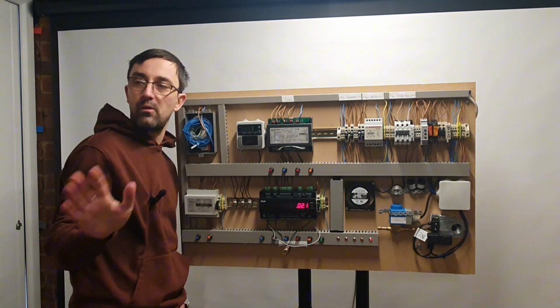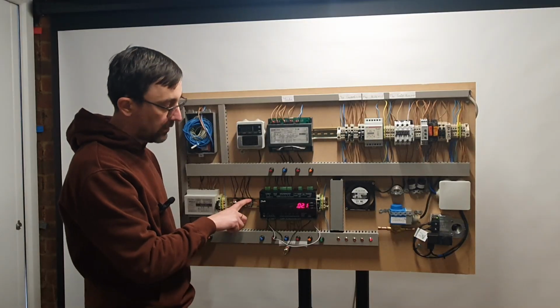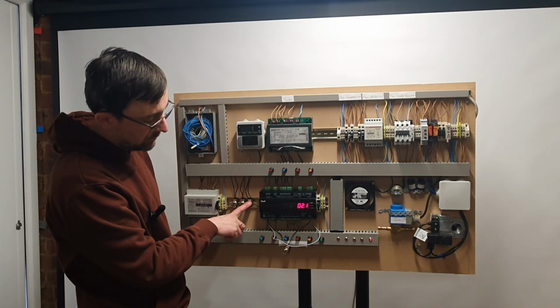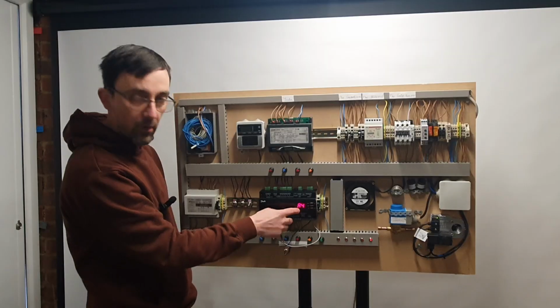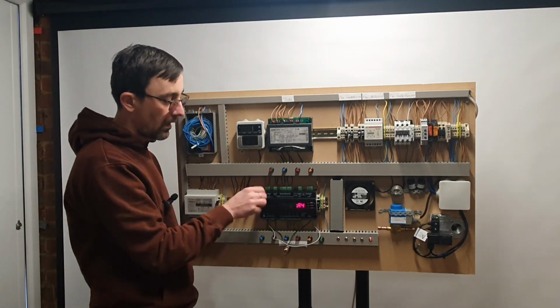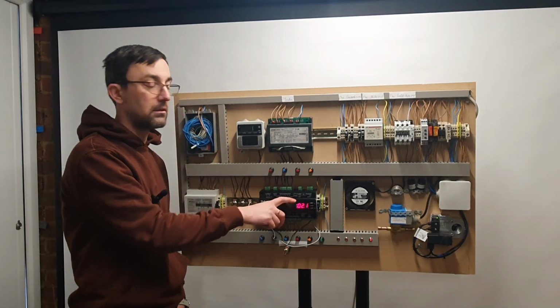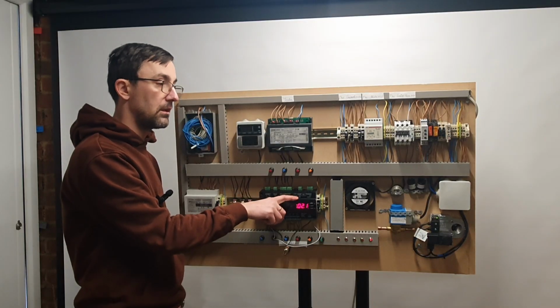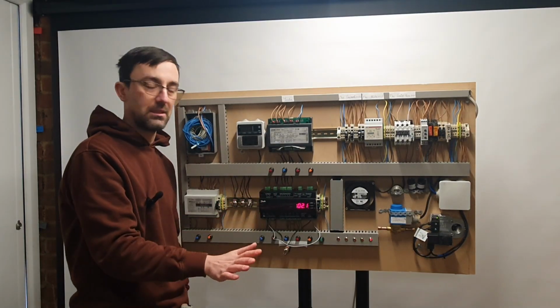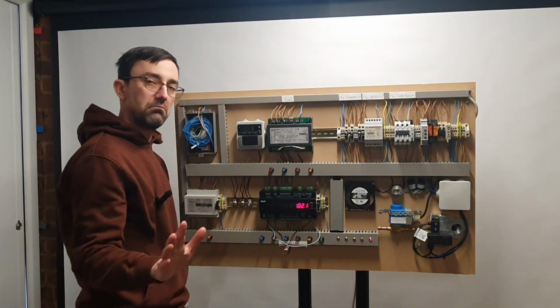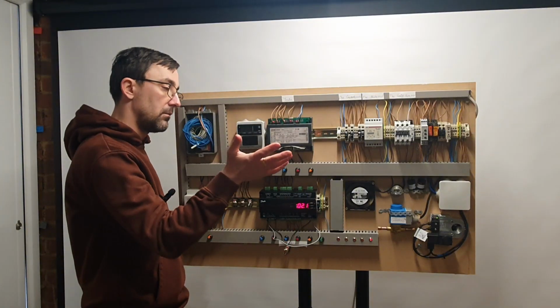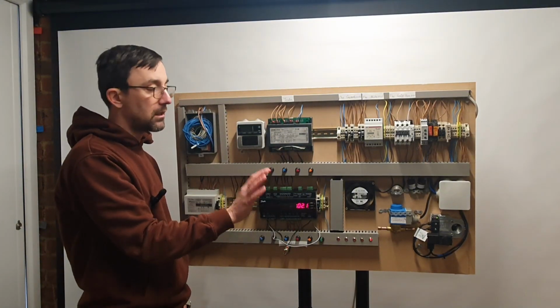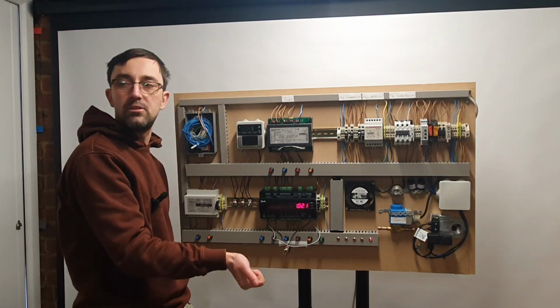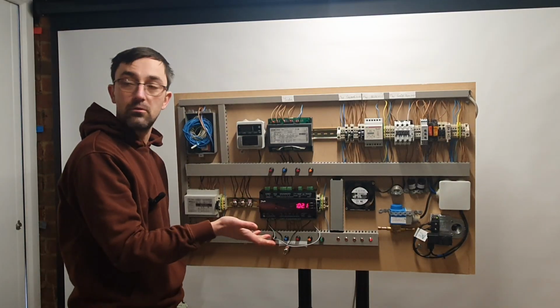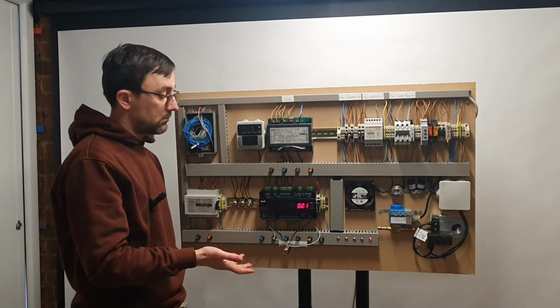So let's just quickly recap. This would be my door switch. A4, door alarm. After a certain period, because of the way I commissioned it, it waits 3 to 5 minutes, and it will bring refrigeration back on. Maybe the customer forgot to fully shut the door. If it's a cold room, it will start cooling down.